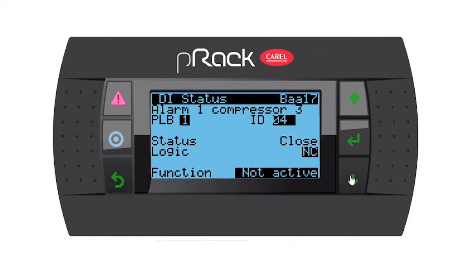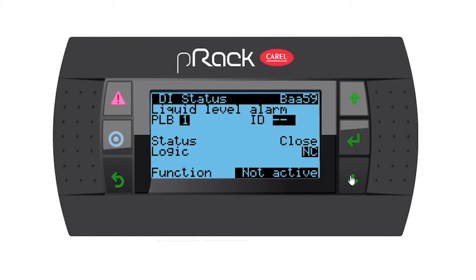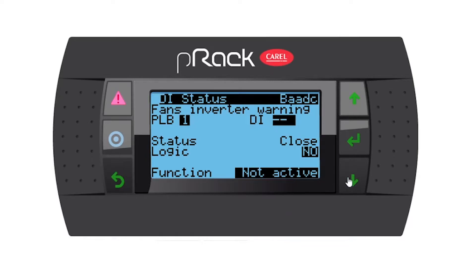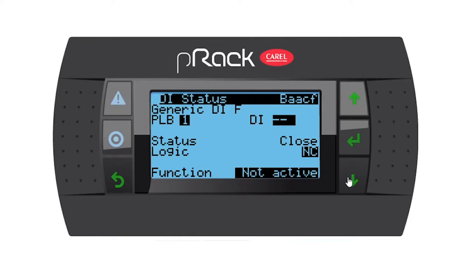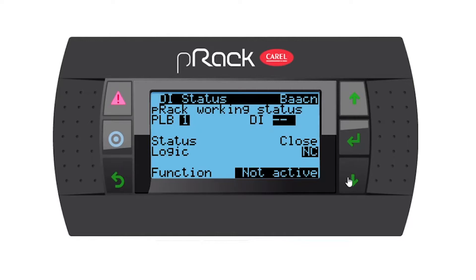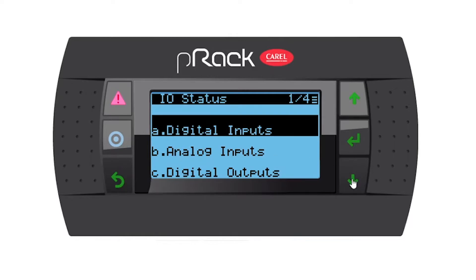I'm leaving my logics as normally closed. Going down, you have the option for a common oil alarm and a liquid level alarm. Yes, we do have a liquid level so I'm going to assign it and leave the logic at normally closed. Further down there are options for fans inverter warning, fans common overload, heat reclaim, generic functions F through J, unit on/off, and pRack working status. That covers our digital inputs, so let's go back and move to analog inputs.